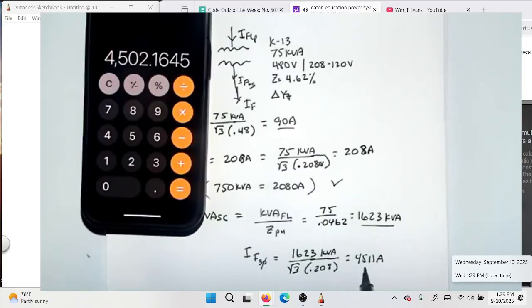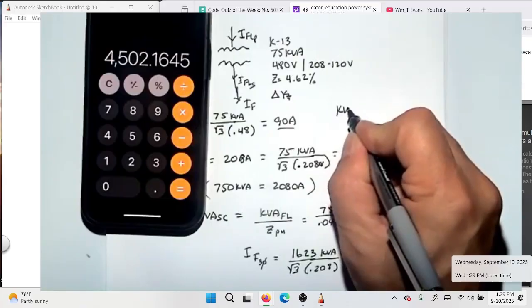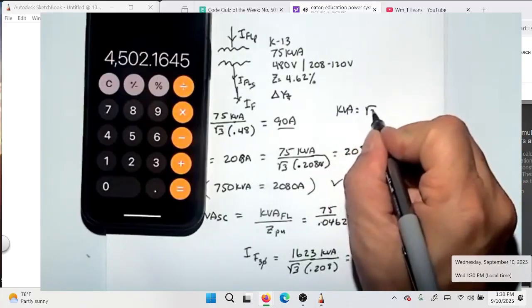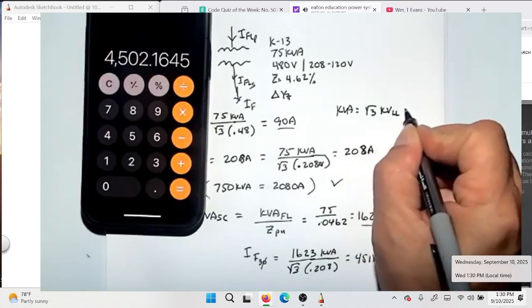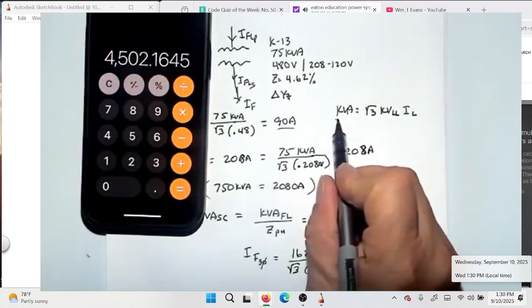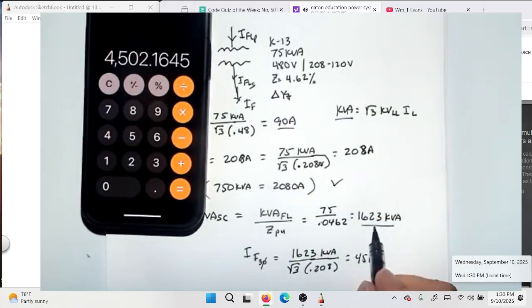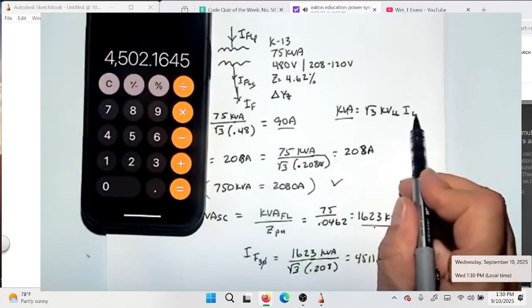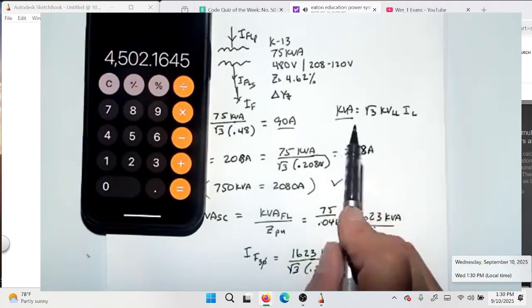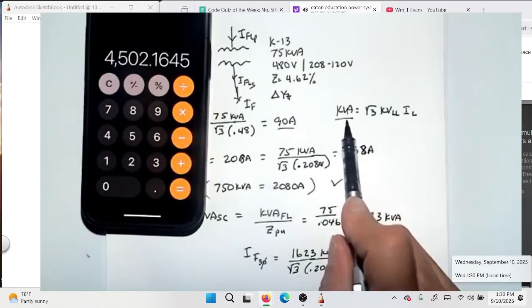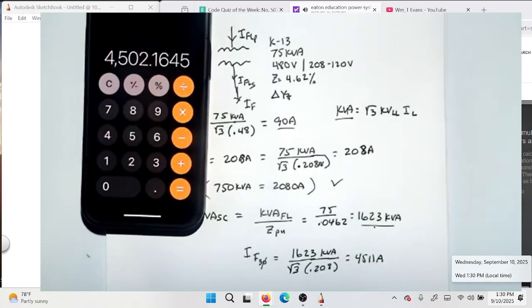But anyway, this number, our full load amps and our fault kVA, are important. And you can see that we're using the same equation, which is kVA equals square root of 3 times kV line to line times I line. If that kVA is our fault kVA, which is what we used here, we can then calculate the fault current here. So the equations are all the same. It's either kVA full load or rated, or kVA fault, and the way you get kVA fault is divided by the impedance. But again, if you can remember that 208 volt and 208 amps, that's going to come in really handy.